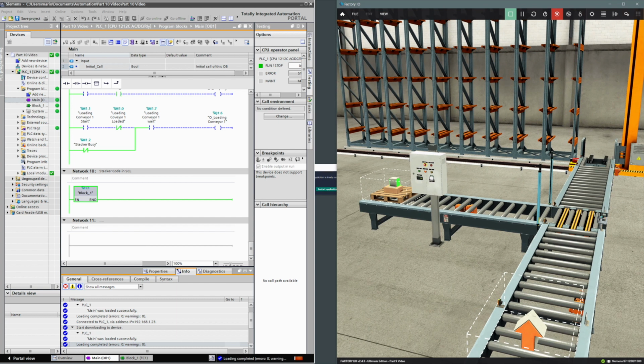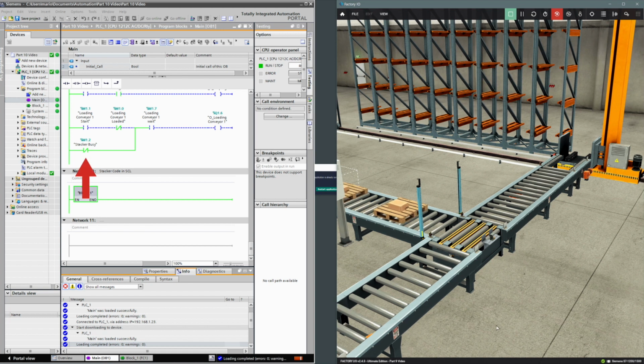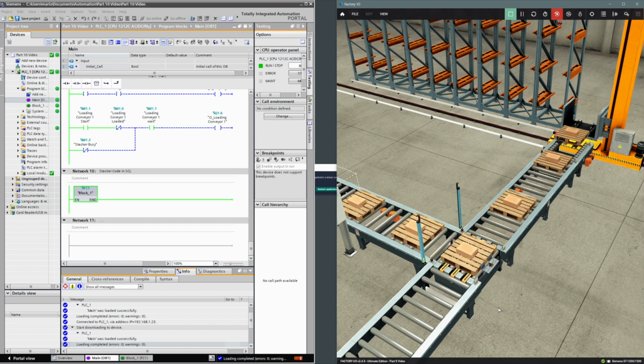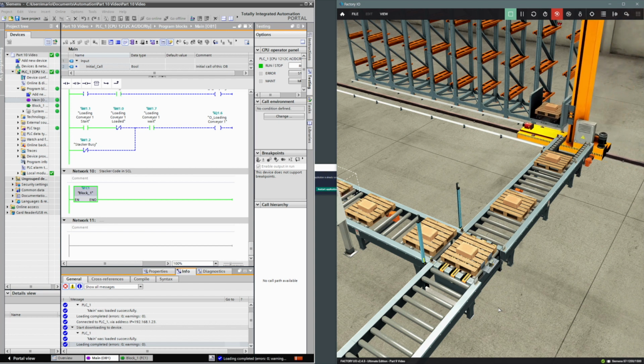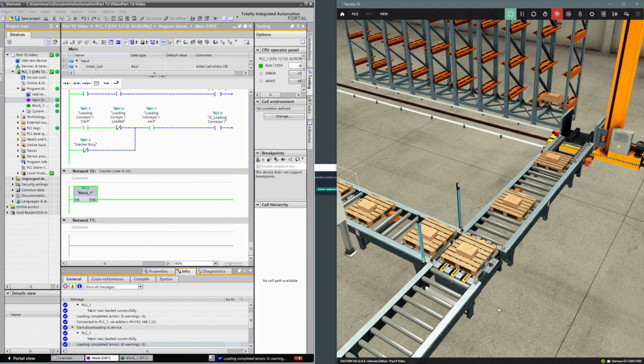Into auto and select the green button. We can see the stacker busy signal M1.2 is not made true yet, and because it's a normally closed contact, we have a signal path up to M1.7. However, as soon as the pallet passes the left entry conveyor, M1.7 loading conveyor wait is made true and will stay true until FactoryIO and the PLC are stopped and both started again. So this has allowed the loading conveyor to wait for a while until a pallet is going towards the small loading conveyor when the system is started up.